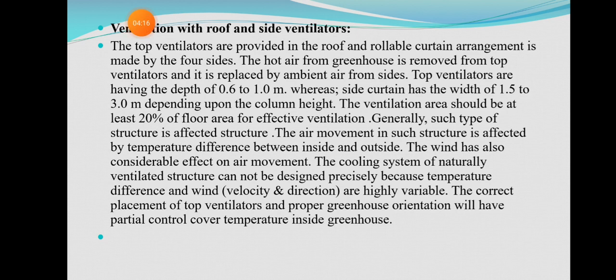The hot air from the greenhouse is removed from the top ventilators and replaced by ambient air from the side. Top ventilators have a depth of 0.6 to 1.0 meter, whereas side curtains have a width of 1.5 to 3 meters. Depending upon the column height, the ventilation should be at least 20% of the floor area for effective ventilation.